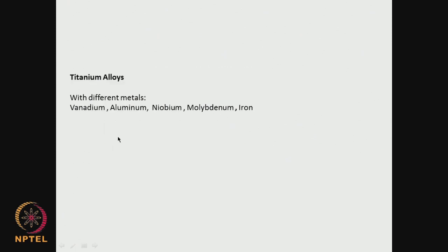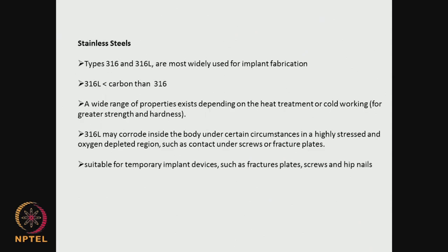Titanium alloys — there are many other metals like vanadium, aluminium, niobium, molybdenum, and iron that are mixed with titanium to form alloys. These alloys have very good properties — they reduce the modulus further and also give shape memory properties. Stainless steel of course is very cheap, so it is widely used — 316 and 316L. The 'L' means it has less carbon, so it is much better than 316. 316L is used in many implants. They give good strength and hardness.